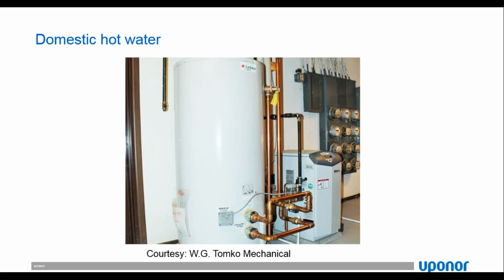And we can also go ahead in this situation and have our boiler heat our domestic hot water at the same time. So now I have my nice 97% efficient boiler heating my domestic hot water versus 85% or 82% on a good day for a water heater. So you get an energy savings from there as well, not to mention it heats much, much quicker.